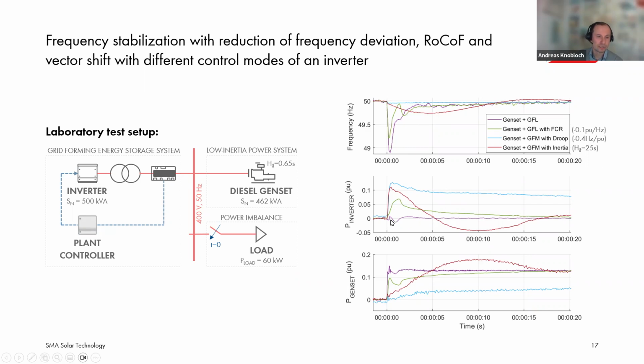We see that the inverter itself, at this load step event with a resulting angular jump, almost does not respond to this grid event with any power. There is some small oscillation, some equalization or resynchronization with the new grid conditions. And the diesel generator absorbs all the instantaneous power that results from this load imbalance event. Due to this power consumption being taken over completely by the diesel generator, we see a high rate of change of frequency, and this is due to the very low inertia constant in our power system.